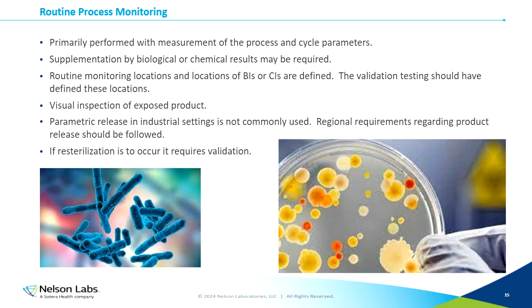I personally have not worked on any processes that are released parametrically, and I am not aware of processes that are released parametrically at this time. Now, that doesn't mean there isn't anything out there, just something I've not seen. So if re-sterilization is to occur, we need to make sure that we build that into our validation testing. And that's why I had mentioned 2X sterilization. That helps us to cover a situation where re-sterilization may need to occur.